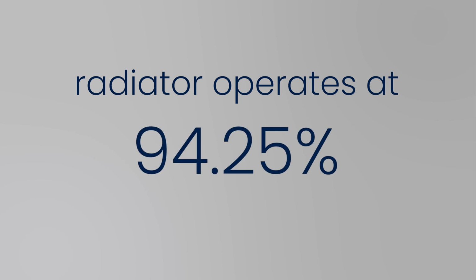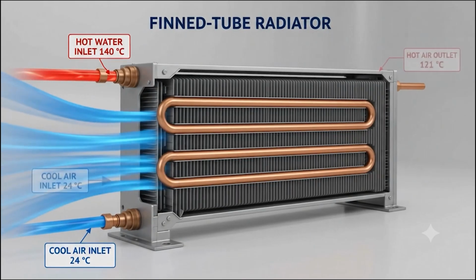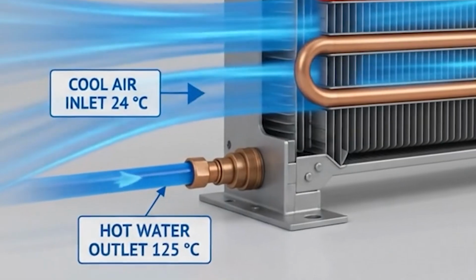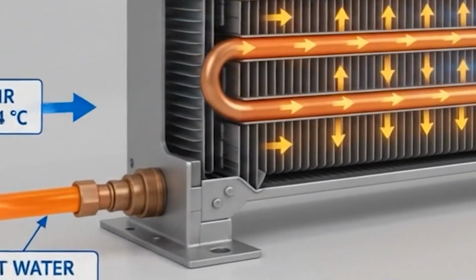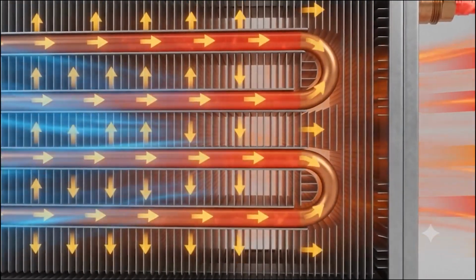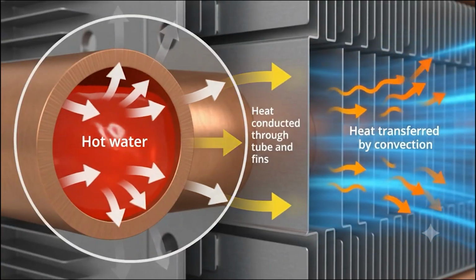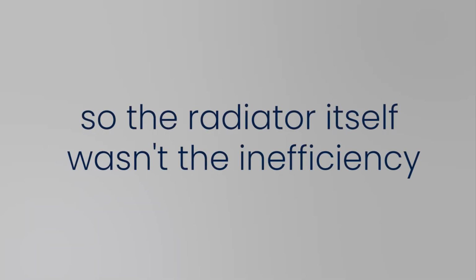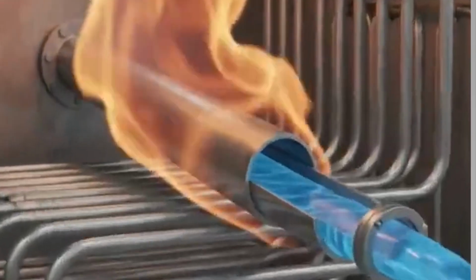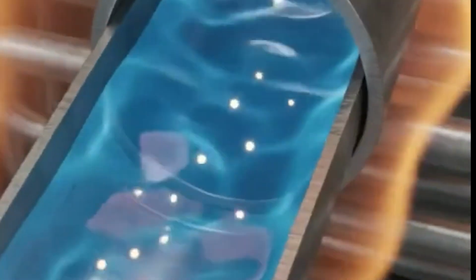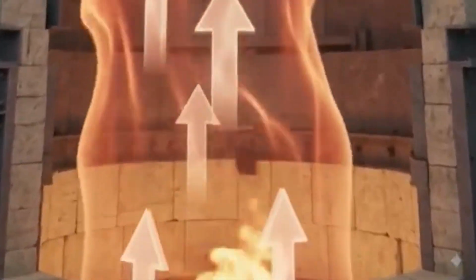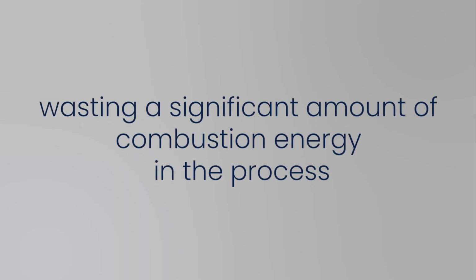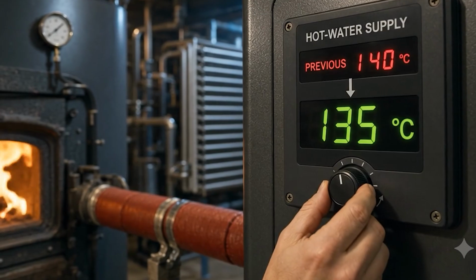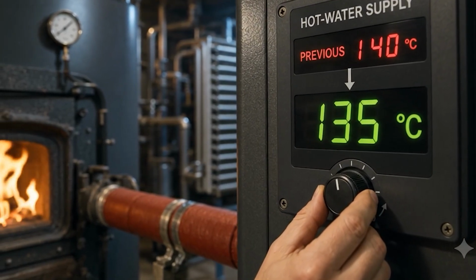The radiator operates at an excellent 94.25% thermal efficiency. Water enters the system at 140 degrees Celsius and leaves at 125 degrees Celsius, heating the drying air from 24 degrees Celsius up to the required 121 degrees Celsius. So the radiator itself wasn't the inefficiency. The real problem was upstream, at the boiler. To supply water at 140 degrees Celsius, the boiler must reject flue gases at very high temperatures, wasting a significant amount of combustion energy in the process. Lowering that supply temperature was the key to real fuel savings.